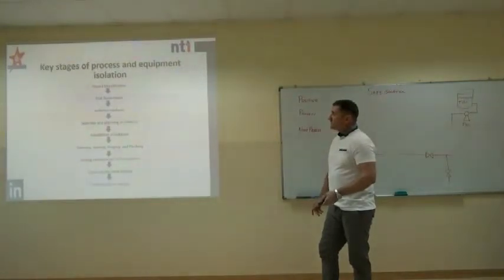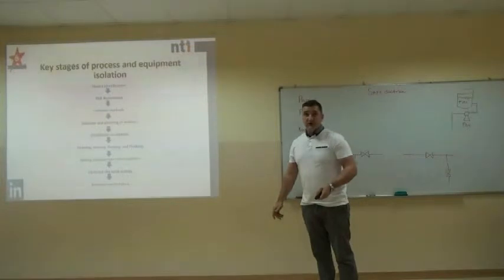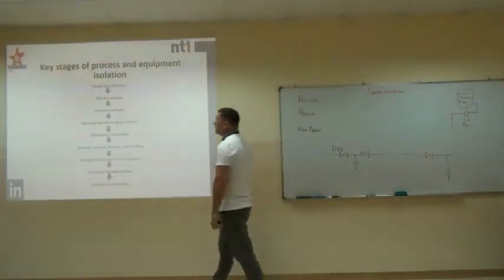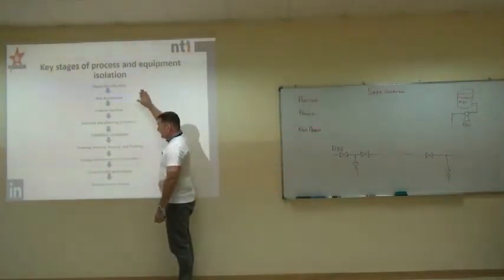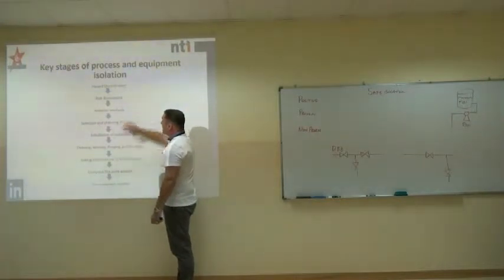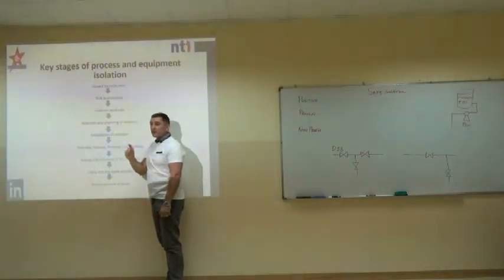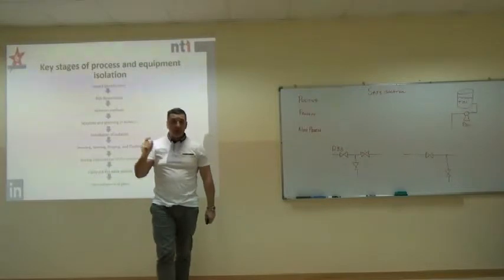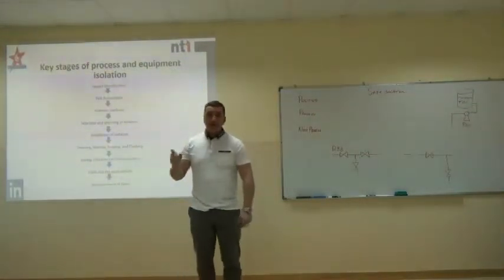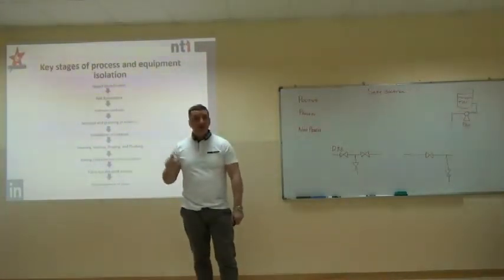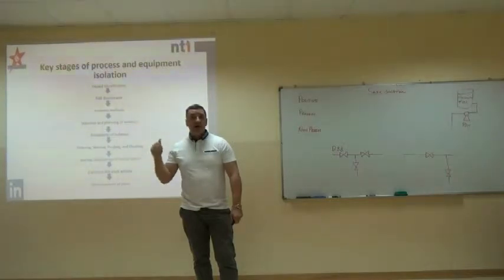This is the process that the Health and Safety Executive and the Energy Institute say we should follow before we isolate anything. Many people say we write the risk assessment first — we don't. We always get out in the field and identify the hazardous energies first, because something could have changed, and it's easy to miss something if we become complacent.